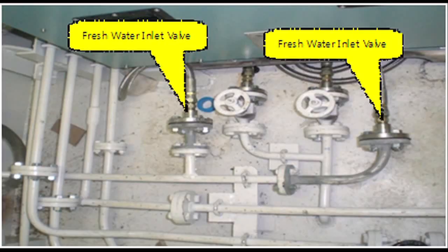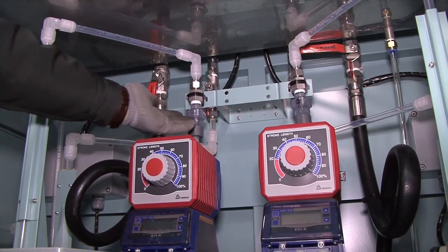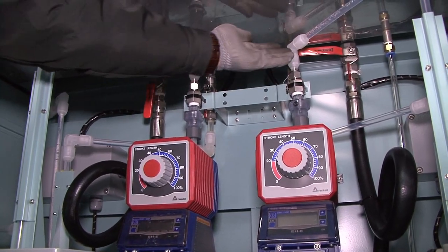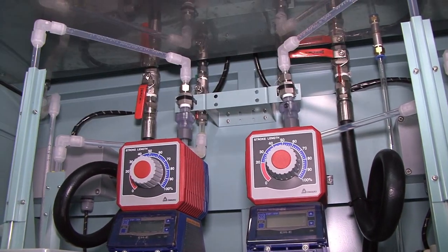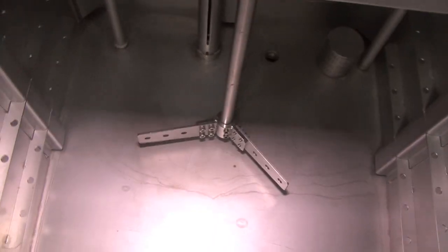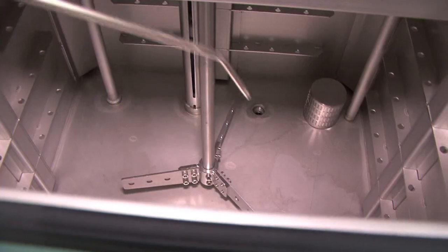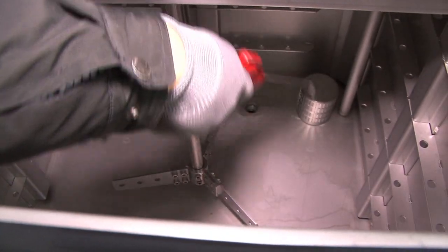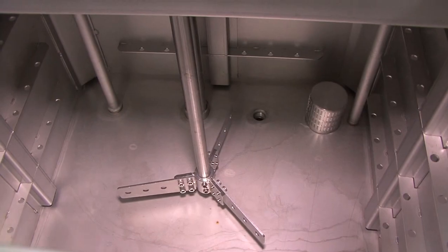Step 2. Close all the inlet valves of fresh water. Step 3. Turn the draining rubber hose at the bottom of ANU facing outward. Open drain valve, right and left side of the tank at the bottom, to drain neutralizing solution from the tank. Use air to clean up ANU strainer. Step 4. Reassemble the front cover and the side cover of ANU.